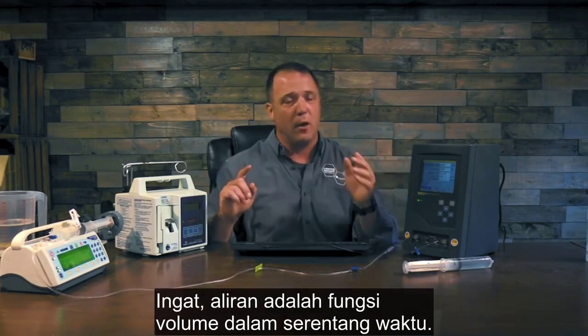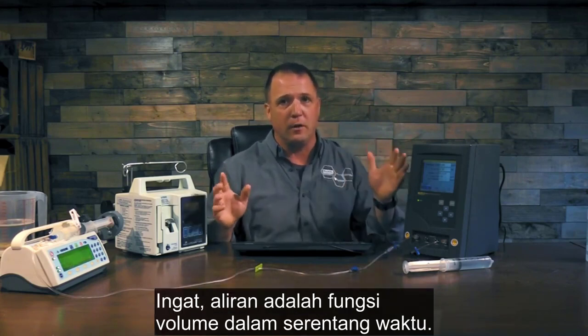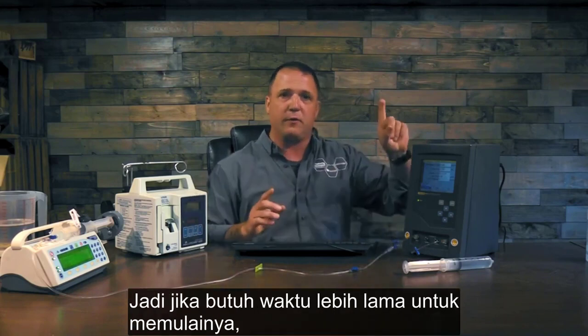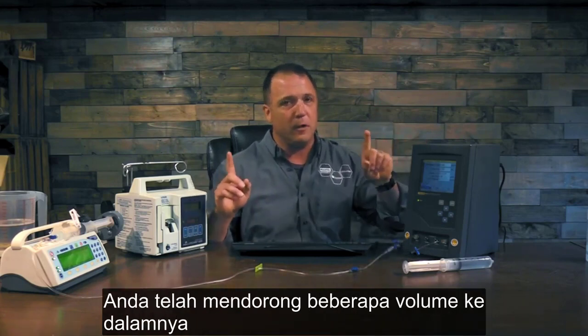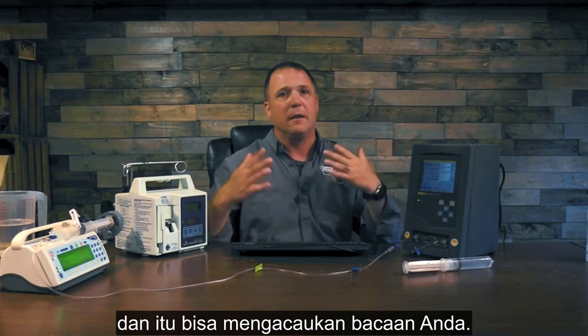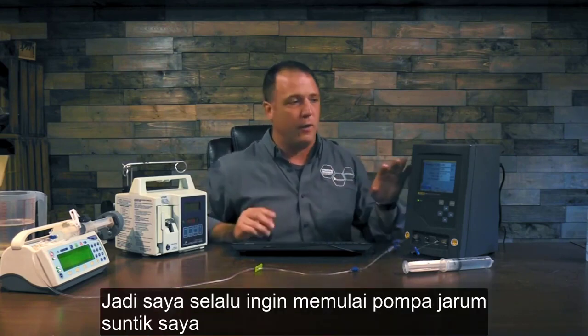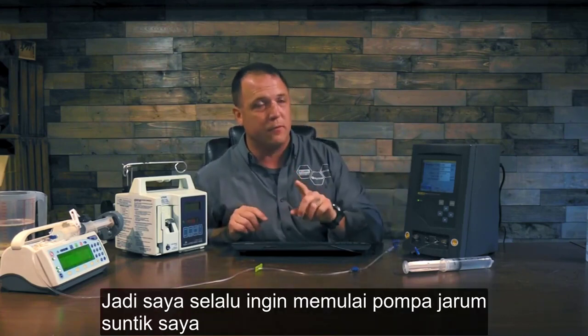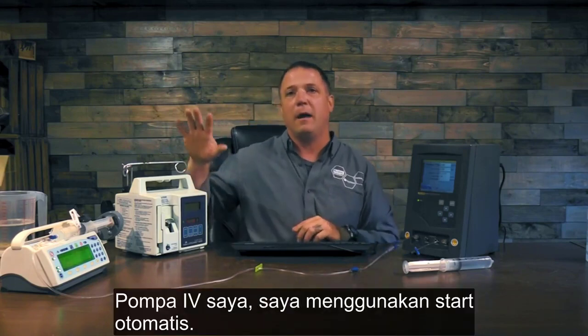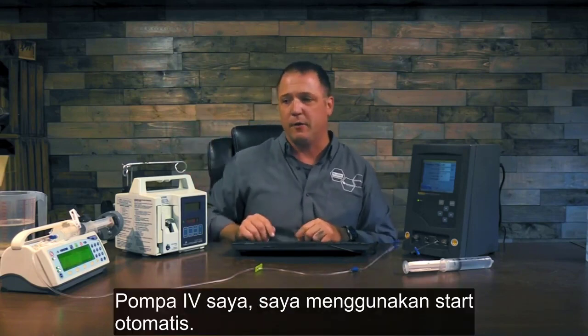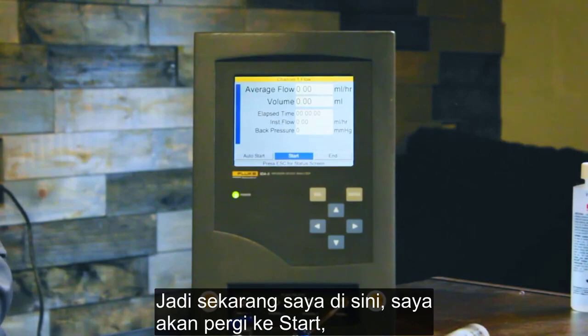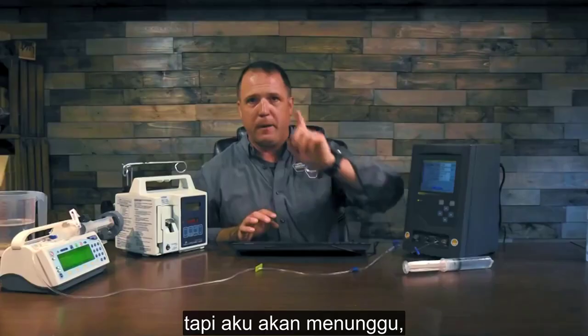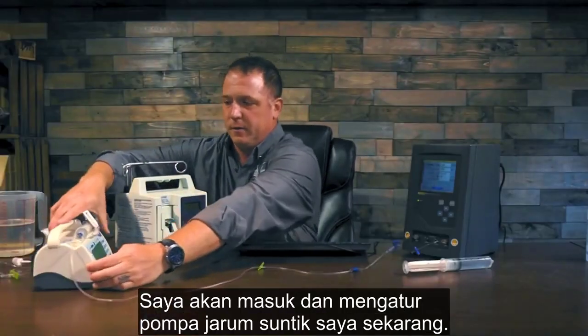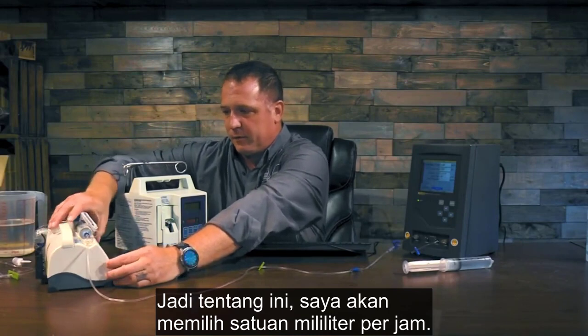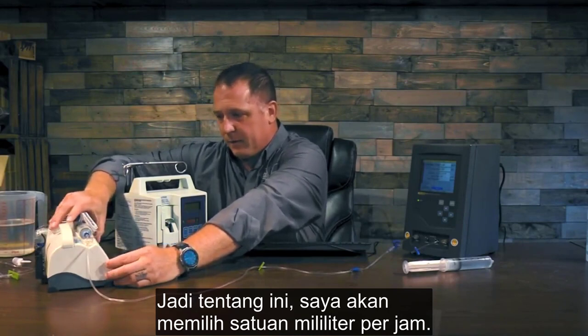Remember, flow is a function of volume over time. So if it takes longer for it to start, you've already pushed some volume into it and it can throw off your readings. That's my personal feeling. So I always like to start my syringe pumps with manual start. My IV pumps, I go ahead and use the automatic start. So now that I'm here, I'm going to go to the start, but I'm going to hold up. I'm going to go ahead and set my syringe pump now. So on this, I'm going to do milliliters per hour.